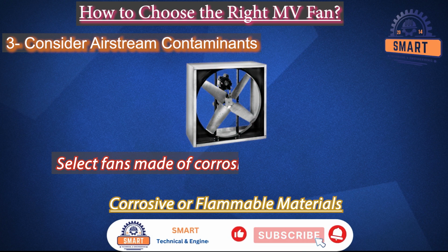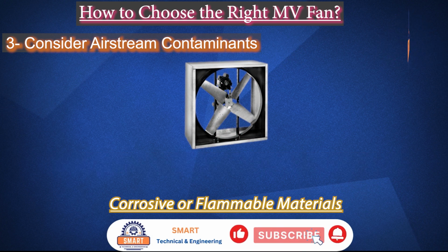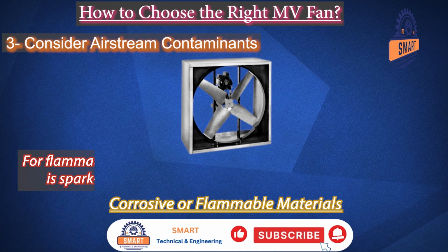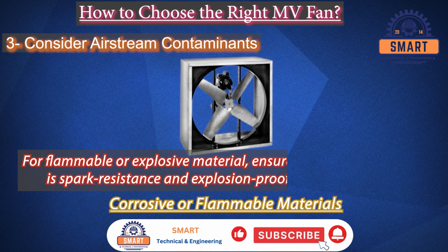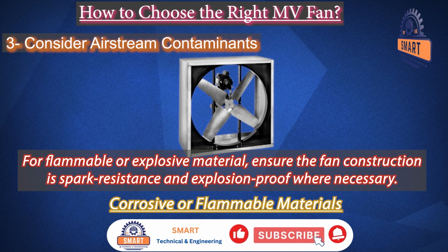Corrosive or flammable materials. Select fans made of corrosion-resistant materials, for example, stainless steel, fiberglass, or with protective coatings. For flammable or explosive materials, ensure the fan construction is spark-resistant and explosion-proof where necessary.